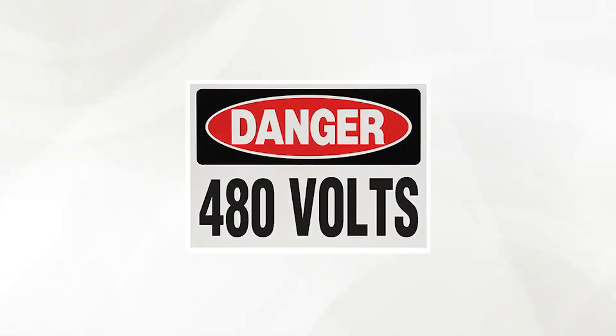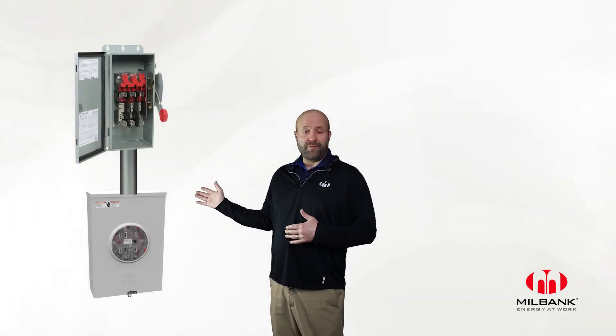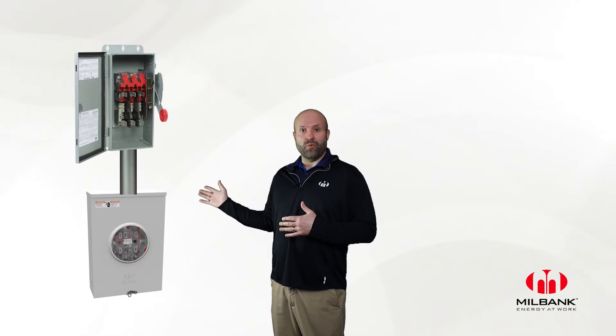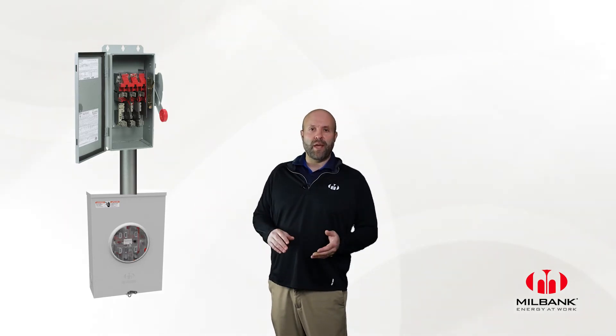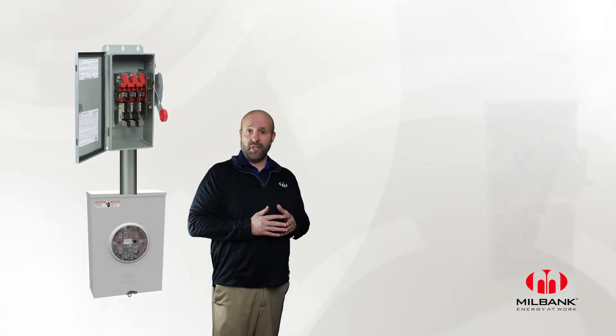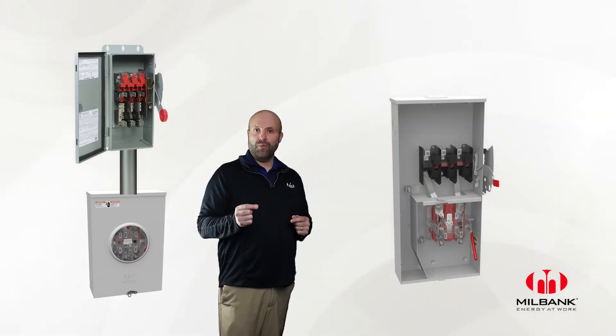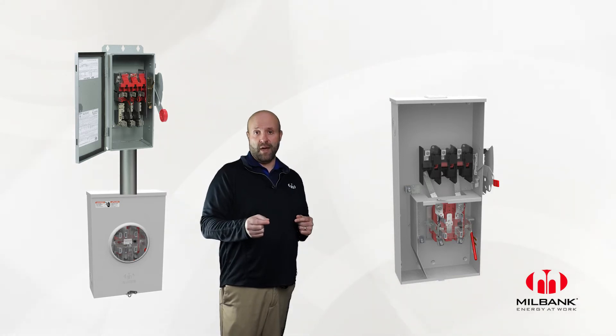Typically, cold sequence is used in 480-volt services, and this can be achieved in a couple of different ways. The first way is the traditional or standalone safety switch in conjunction with an approved Milbank meter socket for that utility. Or the second way is the more efficient, more aesthetically pleasing way by using the new Milbank cold sequence combination.